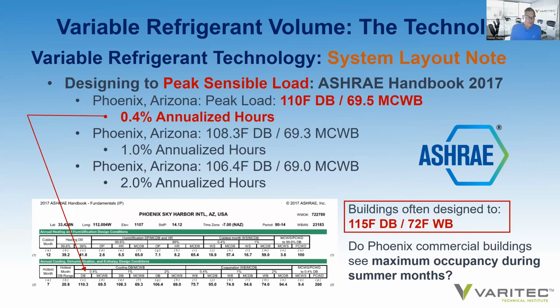If a variable refrigerant system is being designed using ASHRAE's Phoenix, Arizona, Maricopa County design guidelines of 110/69.5 wet bulb, only 0.4% of Phoenix's annualized hours see this peak load, 0.4%. So you're designing a variable refrigerant system to handle this load, compromising its part load efficiency during other times of the year.